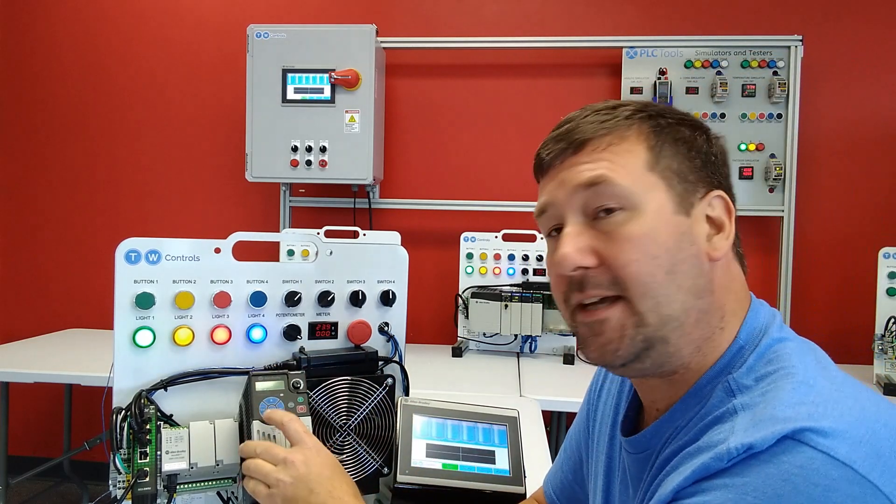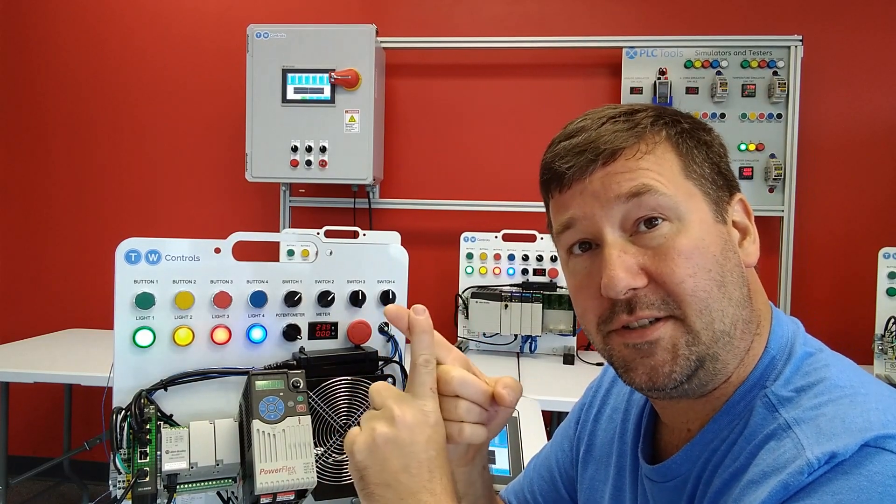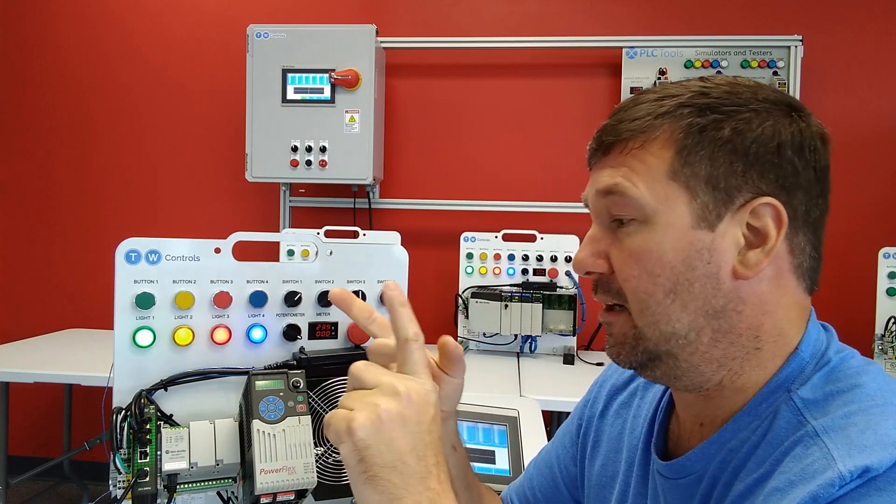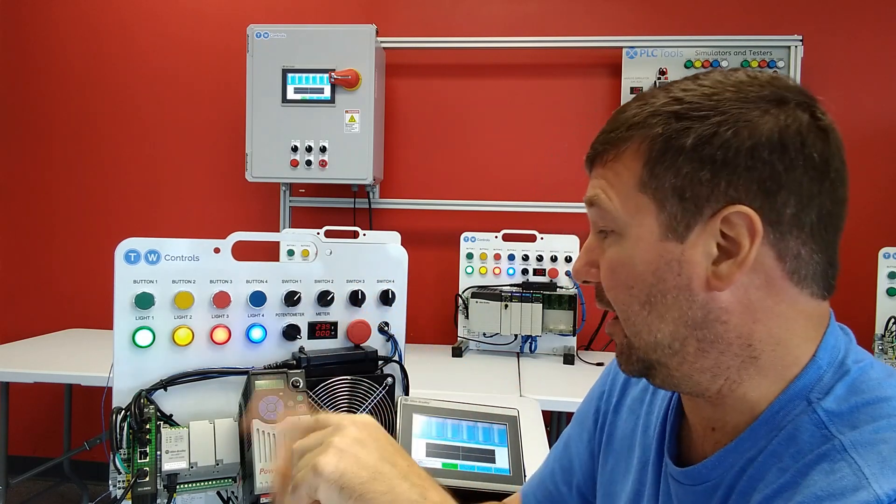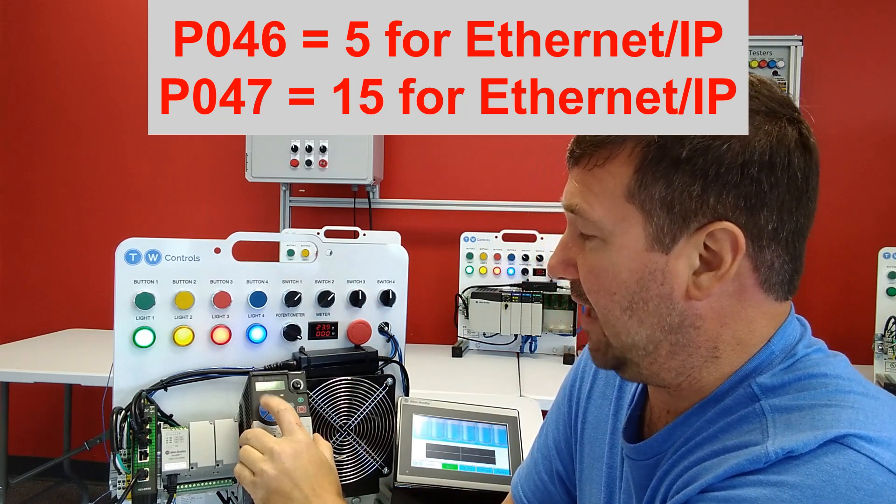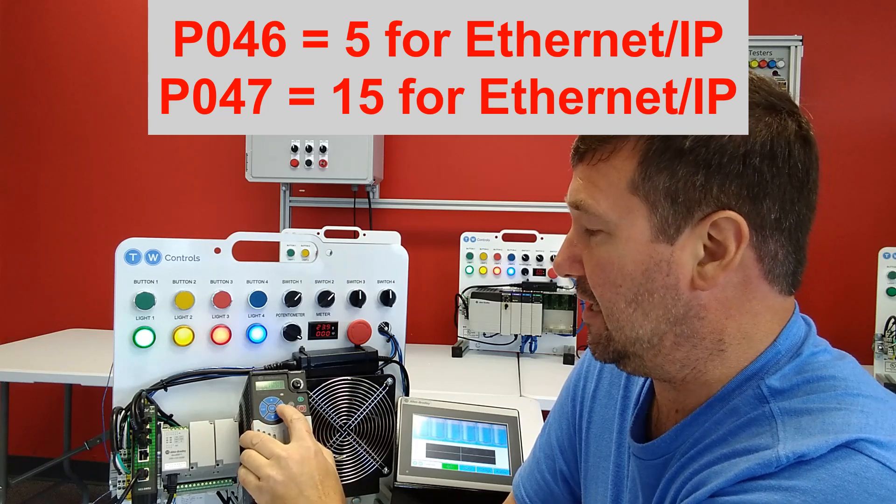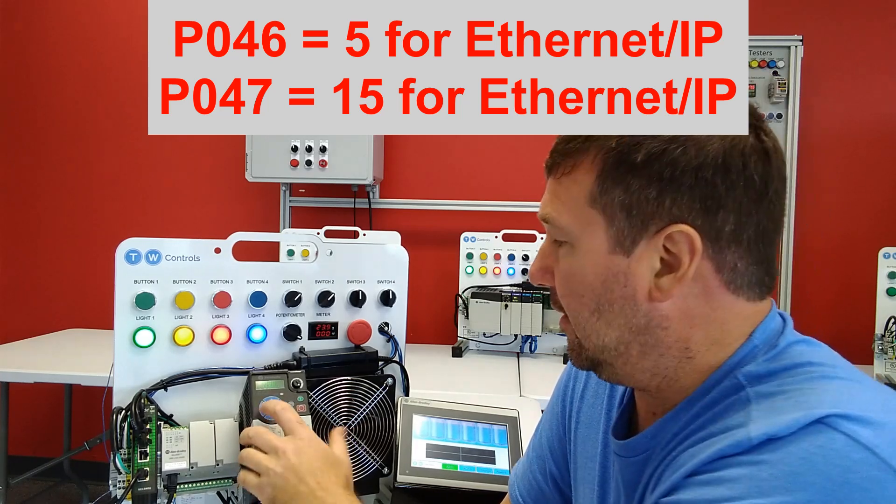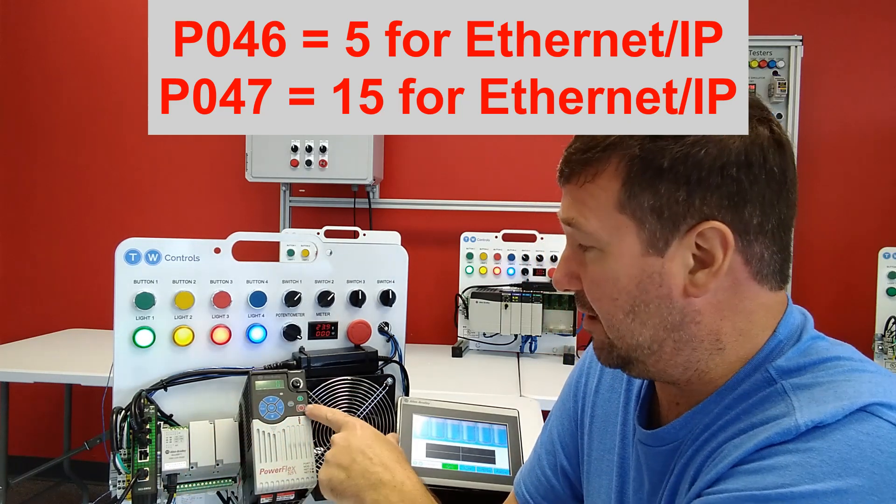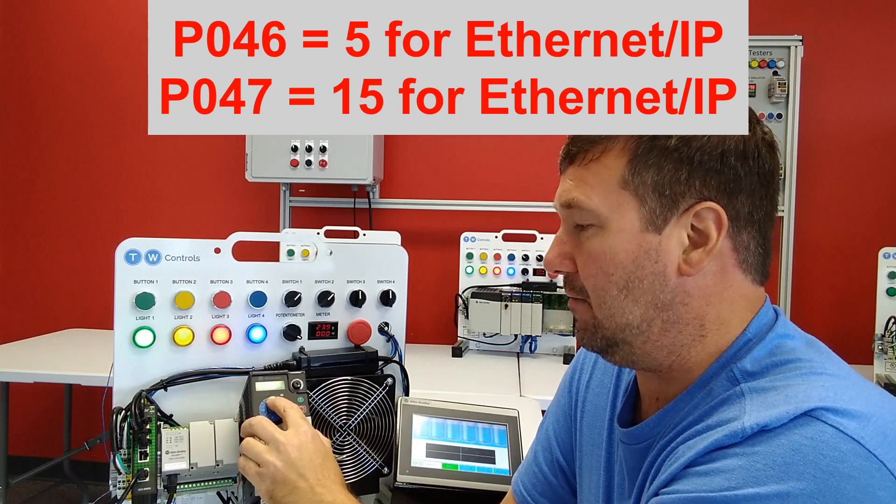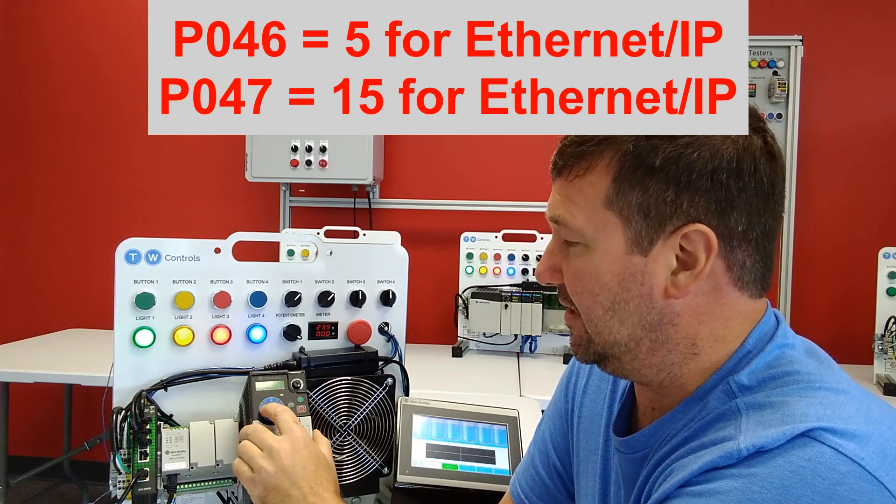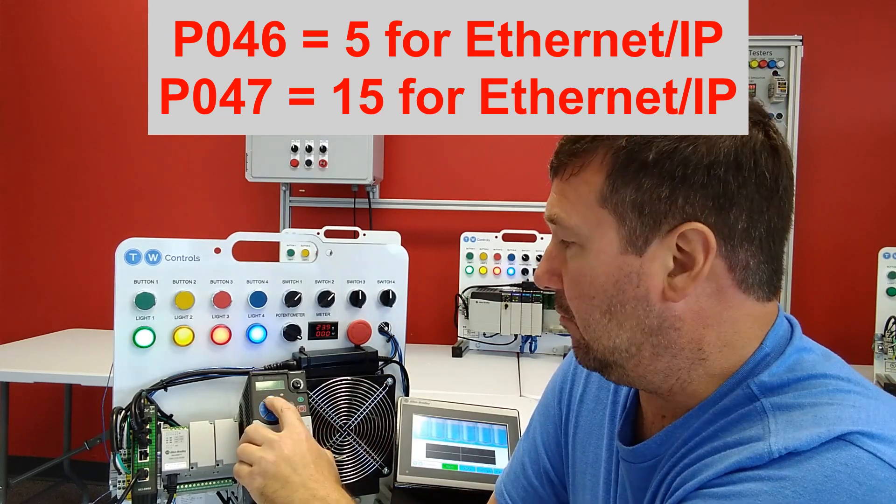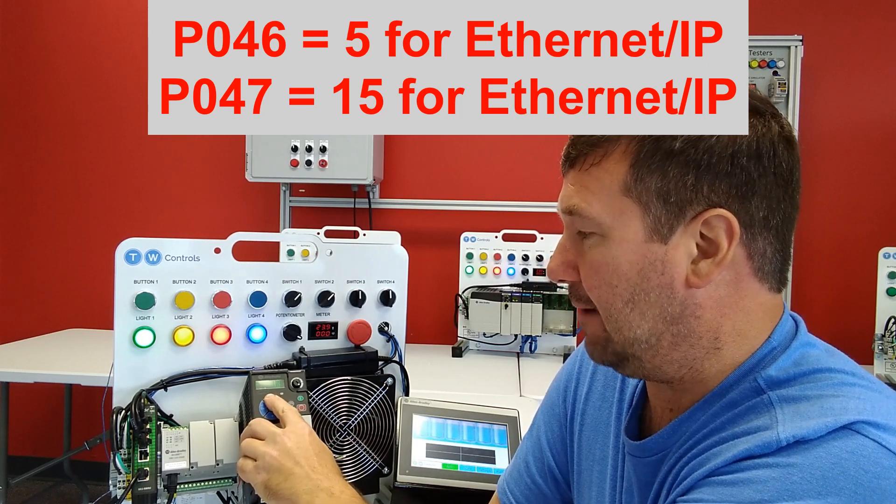And then we need to go to parameter P046. P046 is going to be your control source. And P047 is going to be your speed reference. So let's just hit the select button. Escape to highlight the letter and take it up to P. And let's go down to 46. And P046 is going to be our start mode. Right now it's zero, which is our keypad. We're going to take it to five, which is going to be ethernet IP. And then let's hit the escape button and let's go to P047. We want to set it to 15, which is going to be ethernet IP.